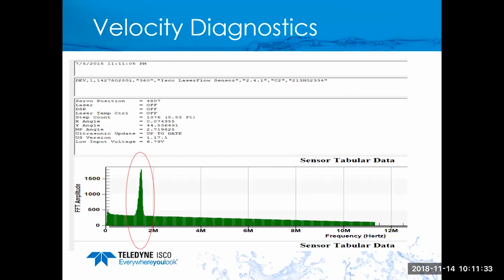This is an actual application where we can look online and we can see, yep, my laser is still working great. I have a real good return signal. Everything agrees on the reading coming back, so I'm confident in my reading. The XY angles, that is the accelerometer portion of this. X should be 0 plus or minus 3, that's the roll, and it's 0.07, so it's right on the nose. Y should be 45 plus or minus 3, it's 44.5.